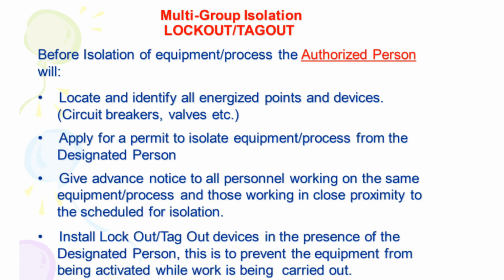Multigroup isolation Lockout Tagout. Before isolation of equipment or process, the authorized person will locate and identify all energized points and devices, circuit breakers, valves etc. Apply for a permit to isolate equipment or process from the designated person. Give advance notice to all personnel working on the same equipment or process and those working in close proximity to the equipment scheduled for isolation. Install Lockout Tagout devices in the presence of the designated person. This is to prevent the equipment from being activated while work is being carried out.